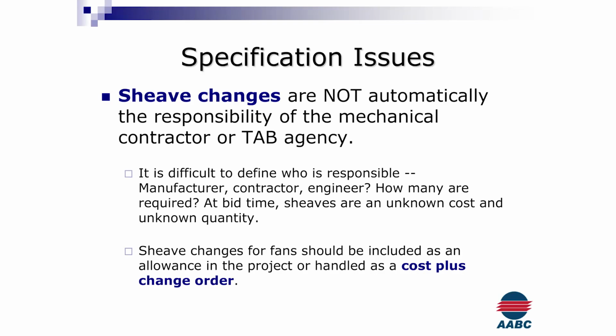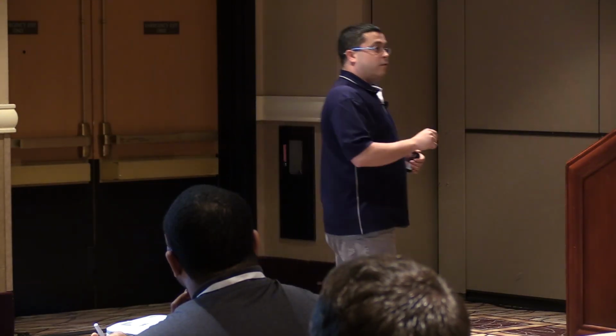Sheave changes are not automatically the responsibility of the mechanical contractor or the TAB agency. We're relying on the fan manufacturers who have all this great software, and they extrapolate all these numbers, and they have all these different model numbers of fans, that when it comes out of that factory, they're claiming that they did it right, and they have this packaged rooftop unit that it's always going to do 5,000 CFM at 3/4 of an inch of static, right? And that's great because they tested that in a laboratory with great straight duct. That doesn't happen in the real world.